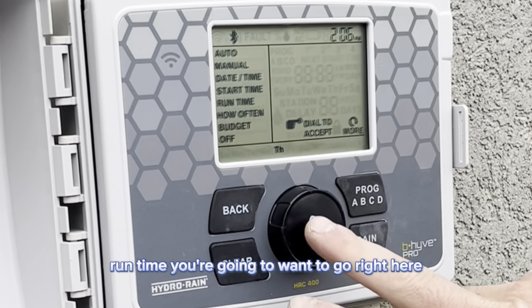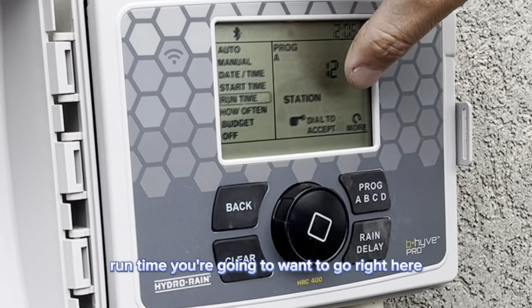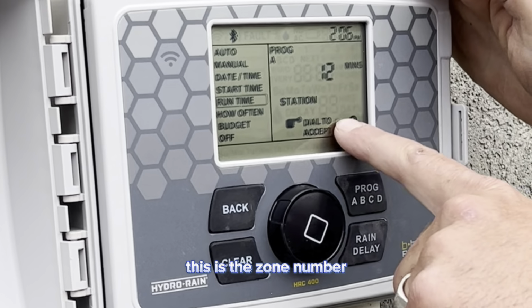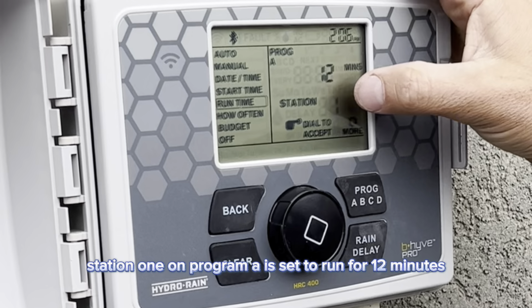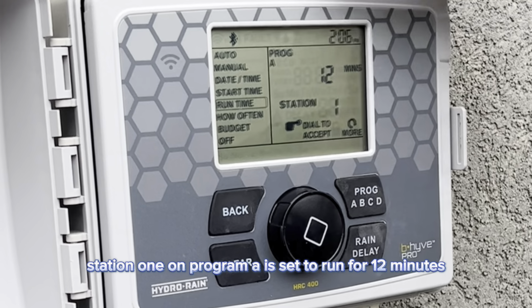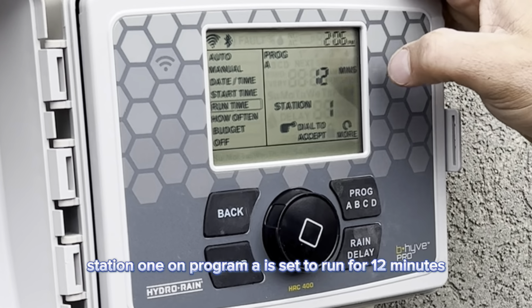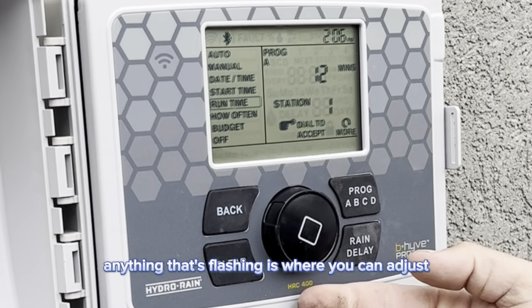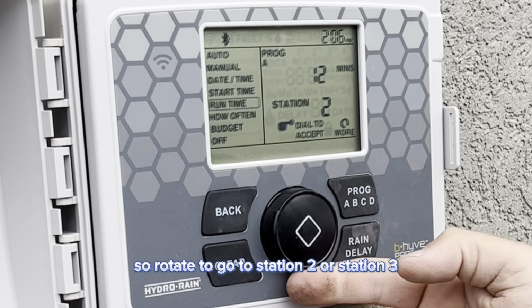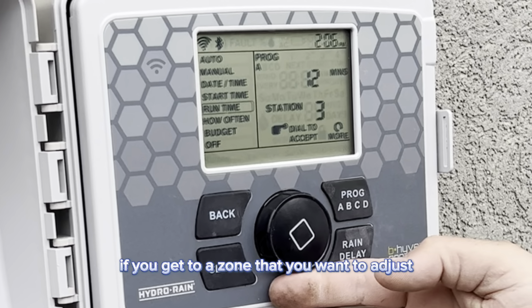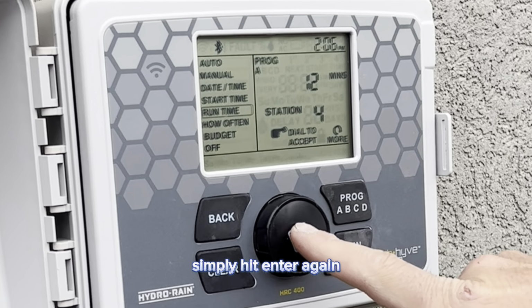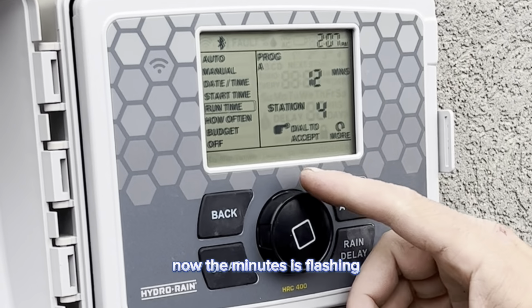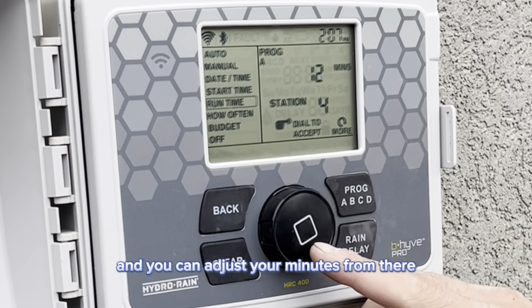Run time. You're going to want to go right here, the one flashing. This is the zone number, station 1. So this is set. Station 1 on program A is set to run for 12 minutes. Anything that's flashing is where you can adjust. So rotate to go to station 2 or station 3. If you get to a zone that you want to adjust, simply hit enter again. Now the minutes is flashing and you can adjust your minutes from there.